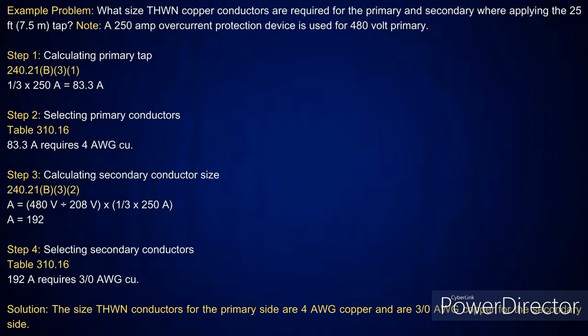All you're going to do here is take the 480 volt, divide the 208 volt into it, and then you take the upstream overcurrent device, which is 250 amps, at what? A third. Now, that's interesting. Why did I divide the 208 volts into the 480 volts? Because it tells me I have to get the ratio. That's right. But I'm still doing the same calculation. The only difference is I'm just getting the ratio, which is 192 amps. I go look at table 310.16 in the 75-degree C column. The next size above that's 200 amps, which is a 3-aught conductor.